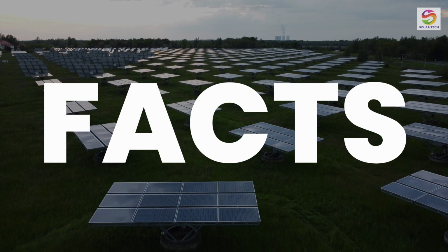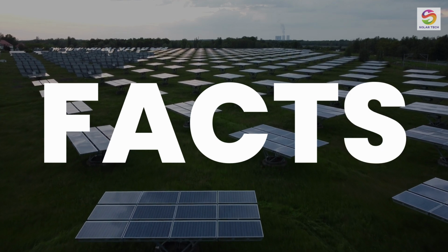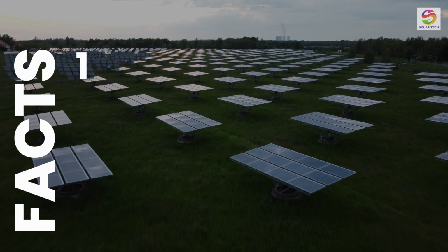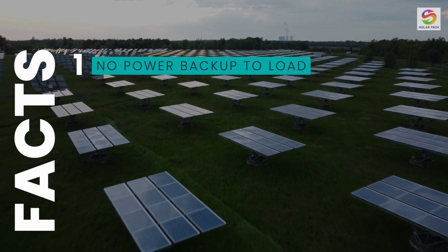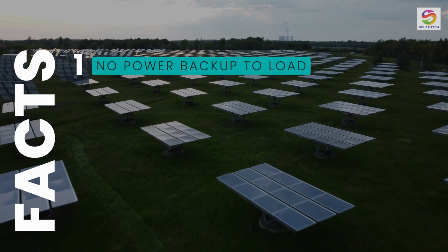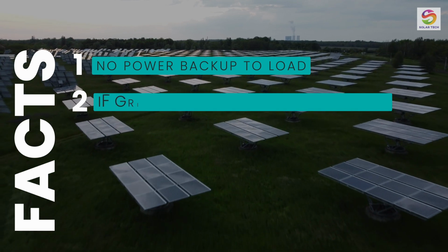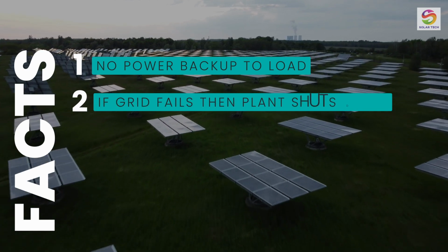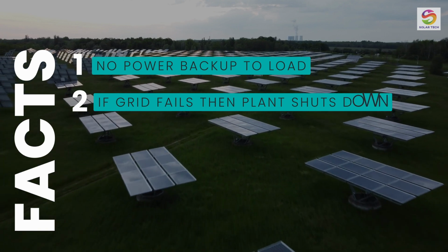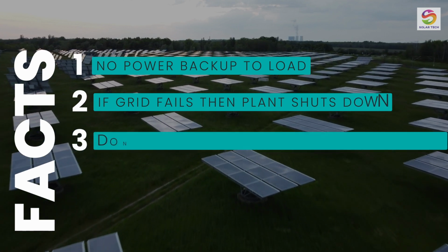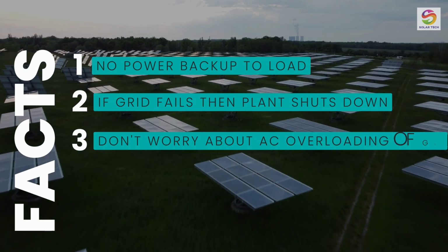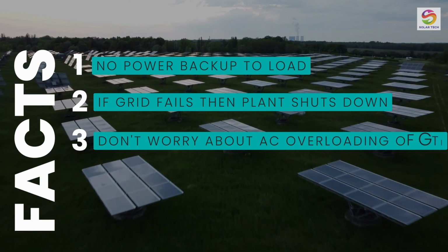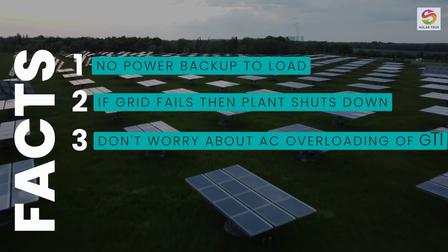Now, let's see some facts about grid tie solar plants. 1. A grid tie solar plant does not provide any power backup to your load. 2. If grid supply fails, then the grid tie inverter shuts down automatically. 3. A grid tie inverter can't be overloaded, as its AC side is directly connected to the grid and the load fulfills the extra requirements from the grid if required.